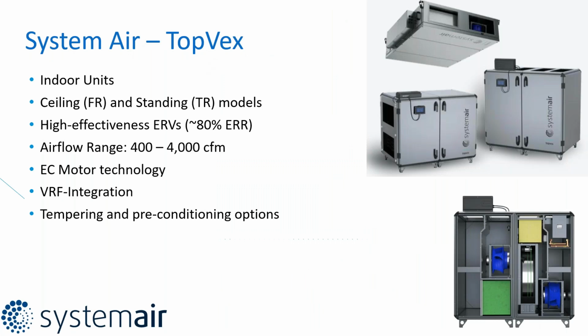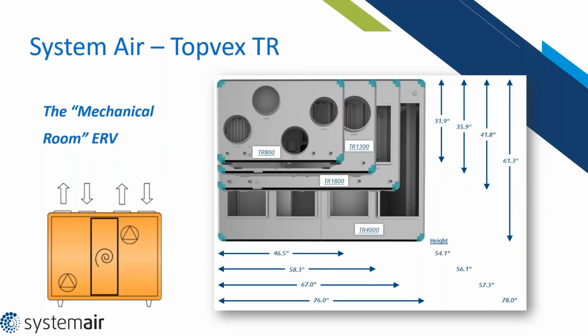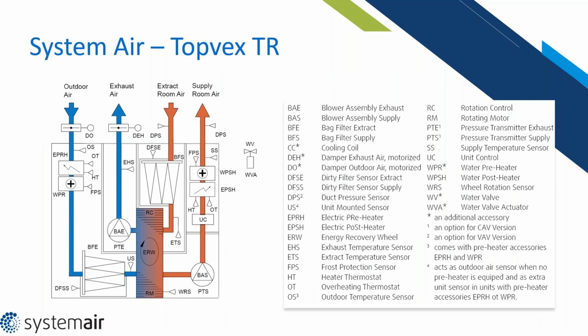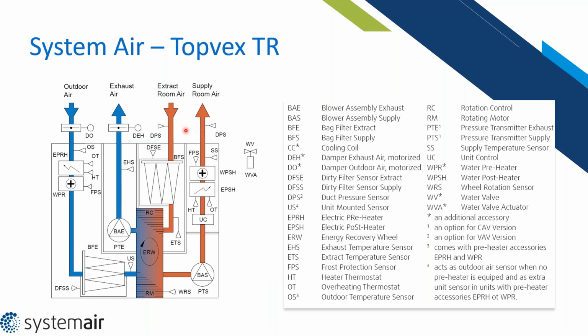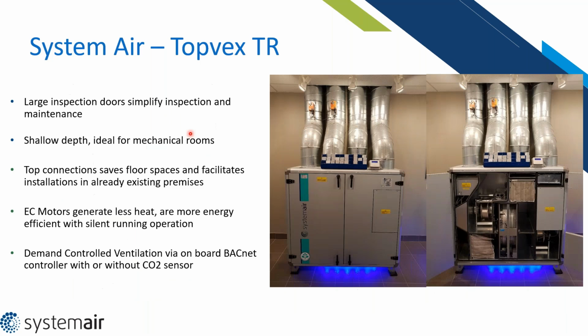So this is the TR, the one that's standing right here. They call it the mechanical room ERV. It's very compact and very configurable, which makes for a pretty good installation. There are a lot of different components. One thing I like to point out is that these can come with 12-inch deep filters. These fans are robust. They needed to make it through that high efficiency wheel and a big filter. And there are some heating options as well. If you were to do a VRF coil, it would go right about here, and then we could mount the LEV kit nearby. This is just an example of what it looks like. Top connections, shallow depth. It's really good for mechanical rooms.